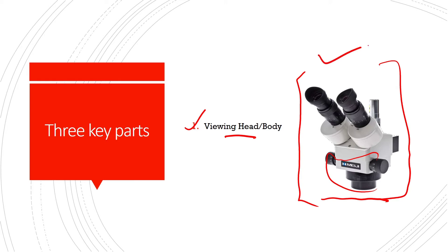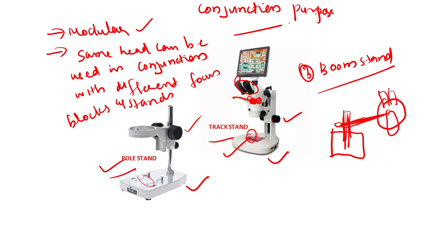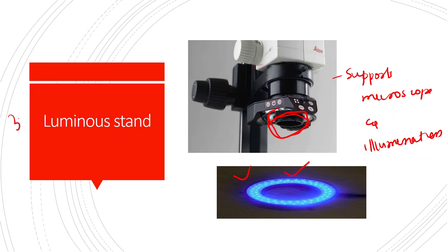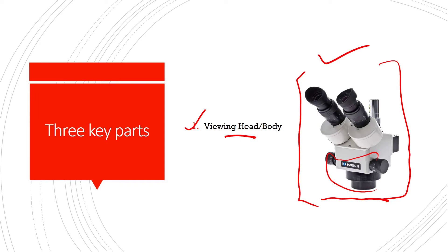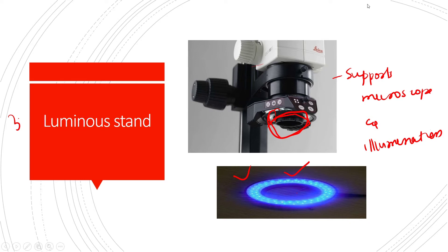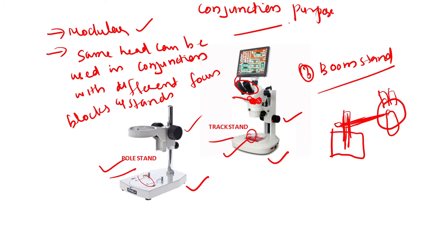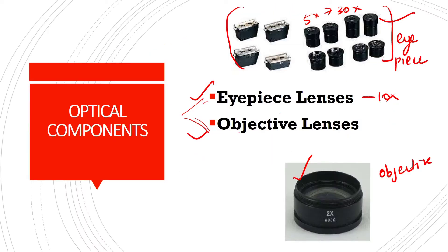The first component is the viewing head or body, which consists of the optical components — the eyepiece lenses and objective lenses. The second is the focus block. The third is the luminous stand, which supports the microscope and provides illumination. The stereoscopic microscope also has a modular design so the same head can be used with different focus blocks and stands — pole stand, track stand, and boom stand.